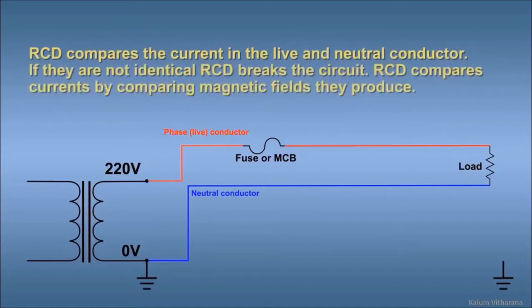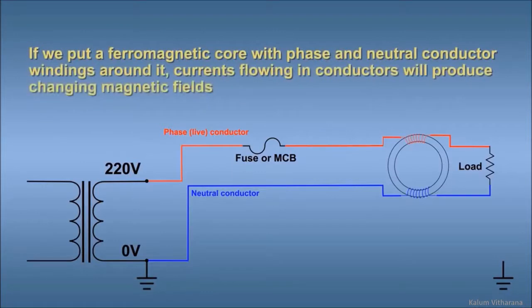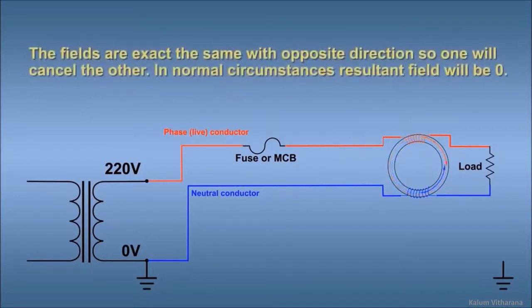RCD compares the current in the live and neutral conductor. If they are not identical, RCD breaks the circuit. RCD compares currents by comparing the magnetic fields they produce. If we put a ferromagnetic core, and phase and neutral conductor form windings around it, currents flowing in the conductors will produce a changing magnetic field. The fields are exactly the same with opposite directions, so one will cancel the other. In normal circumstances, the resultant field will be zero.